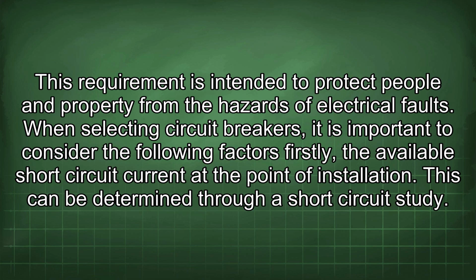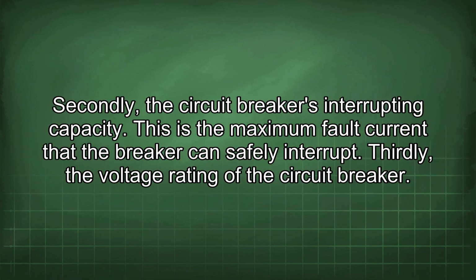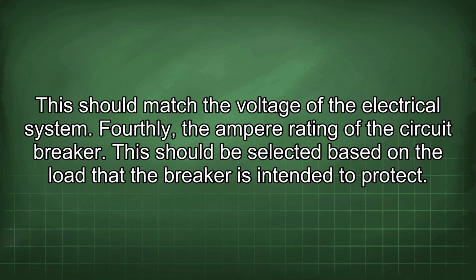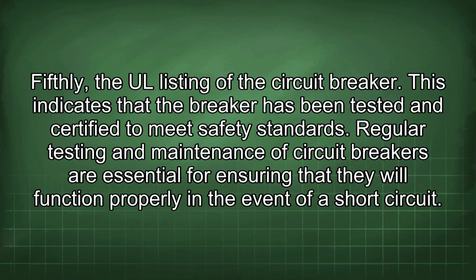When selecting circuit breakers, it is important to consider the following factors. Firstly, the available short-circuit current at the point of installation. This can be determined through a short-circuit study. Secondly, the circuit breaker's interrupting capacity. This is the maximum fault current that the breaker can safely interrupt. Thirdly, the voltage rating of the circuit breaker. This should match the voltage of the electrical system. Fourthly, the ampere rating of the circuit breaker. This should be selected based on the load that the breaker is intended to protect. Fifthly, the UL listing of the circuit breaker. This indicates that the breaker has been tested and certified to meet safety standards.